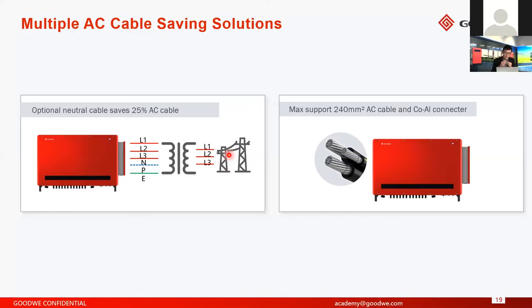Also, as you know, copper cable is much more expensive than aluminum cable. So if you want to use aluminum cable on the AC side, that's fine. For example, the HT series can support a maximum of 240 square millimeters. So you can use aluminum cable, because the AC connector size is much bigger than the aluminum cable you want to use.